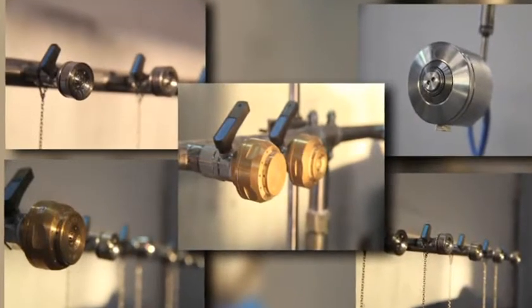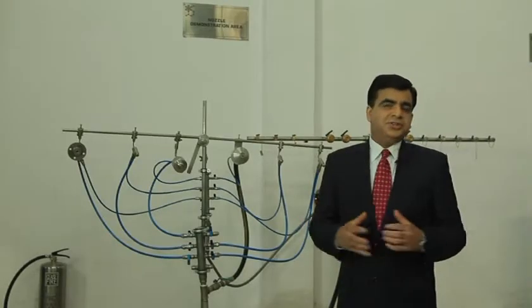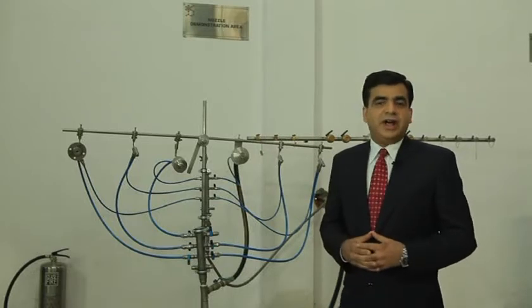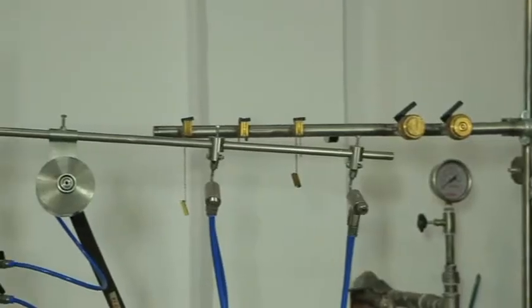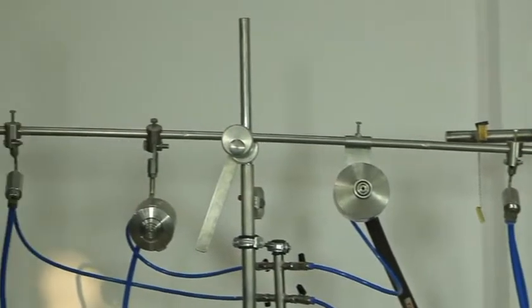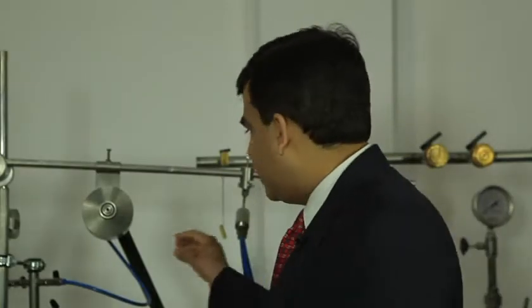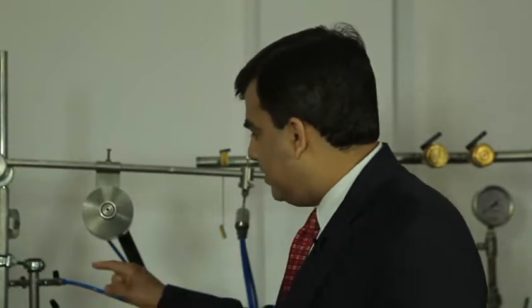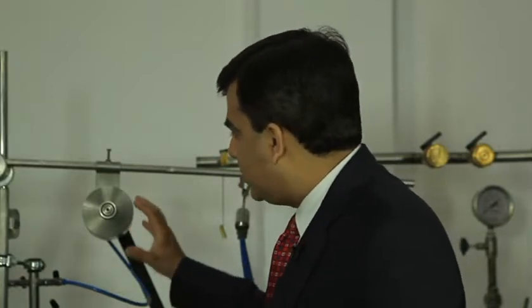First, water is pumped through specially designed nozzles that break water down into minuscule particles. Here's the nozzle demonstration area at the Ceasefire AI lab. There are special nozzles for single fluid systems. Twin fluid systems need separate pipes, one for nitrogen gas or compressed air, and the other for water. Both of these come together at the nozzle point and get converted into water mist.